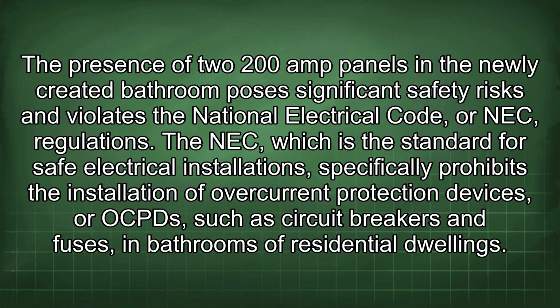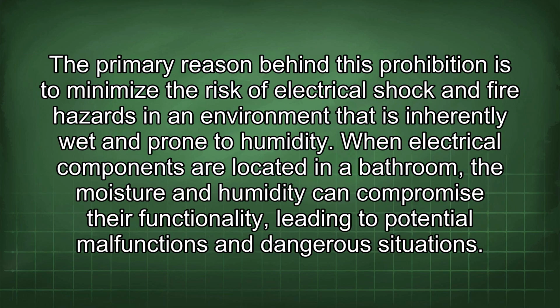The presence of two 200-amp panels in the newly created bathroom poses significant safety risks and violates the National Electrical Code, or NEC, regulations. The NEC, which is the standard for safe electrical installations, specifically prohibits the installation of overcurrent protection devices, or OCPDs, such as circuit breakers and fuses, in bathrooms of residential dwellings. The primary reason behind this prohibition is to minimize the risk of electrical shock and fire hazard in an environment that is inherently wet and prone to humidity.